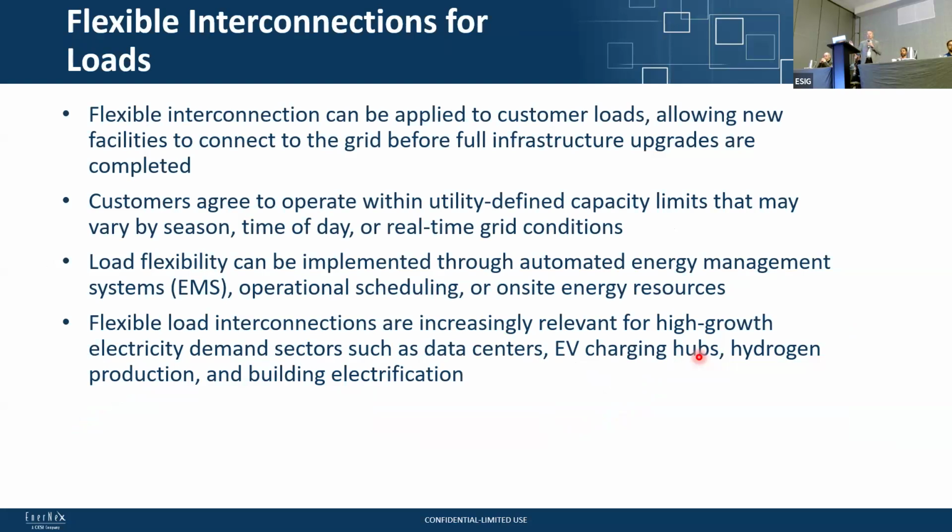So in the reverse direction, large loads could also be thought of as flexible interconnections. Basically, you do a system analysis, and then based on that, the customer may have to agree to operate within defined capacity limits that may vary by season, time of day, or real-time grid conditions. Again, this can be either time-based or more real-time, depending on what you have in place.